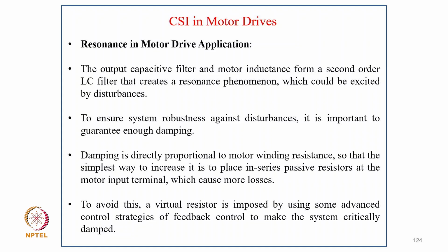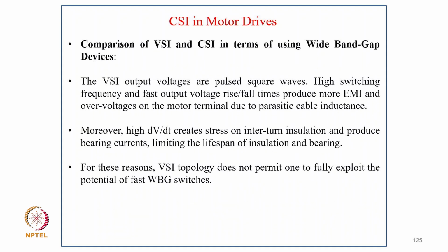Coming to resonance in motor drive applications, the output capacitor filter and the motor inductance form a second order LC filter that creates a resonance phenomenon which could be excited by disturbances. To ensure system robustness against disturbances, it is important to guarantee enough damping. The damping is directly proportional to the motor winding resistance, so the simplest way to increase it is to place passive resistors in series at the motor input terminal, which causes more losses. To avoid this, a virtual resistor is imposed by using an advanced feedback control strategy to make the system critically damped.